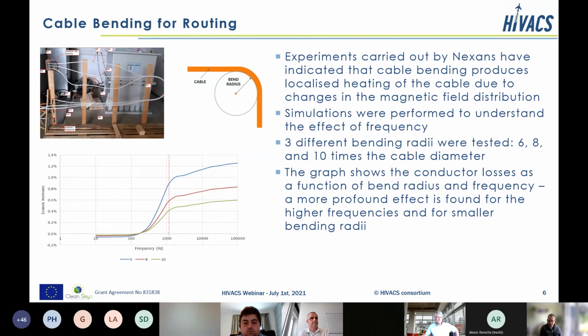And you can see this as a function of frequency. Of course, we're interested in higher frequencies potentially because we may have an AC system operating at, say, 1 kilohertz, 1.5 kilohertz, 2 kilohertz. But you can see if we go through a tight bend radius, then at those kind of frequencies, at the kilohertz level, we can certainly get a 1% increase in our losses in the locality of that bend as a result of the proximity effect influencing the current flow.